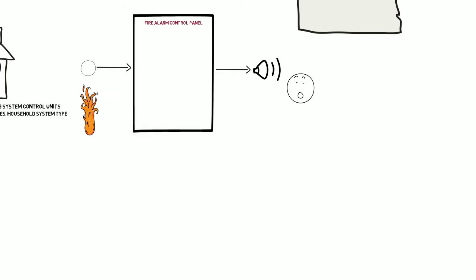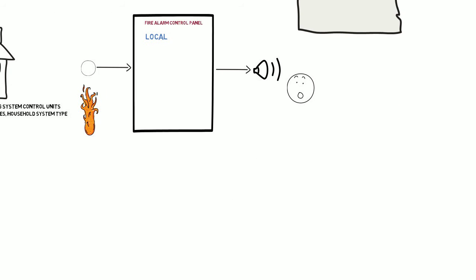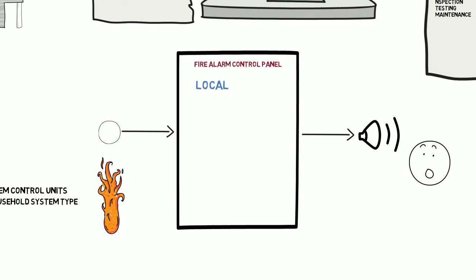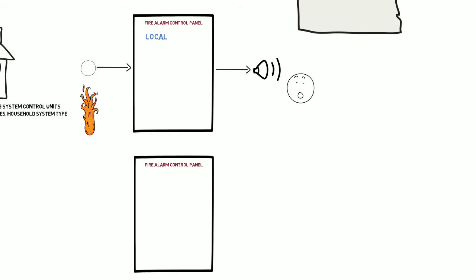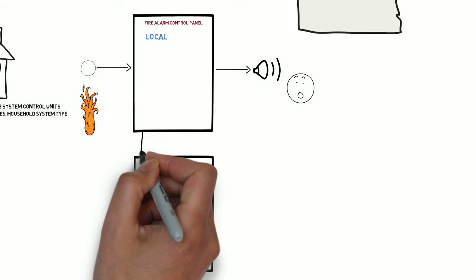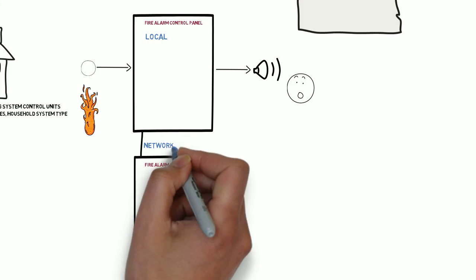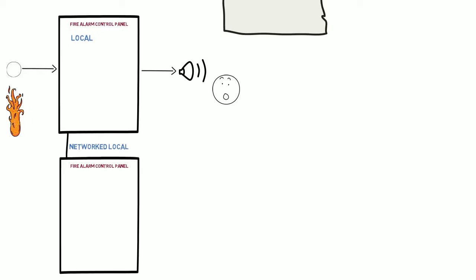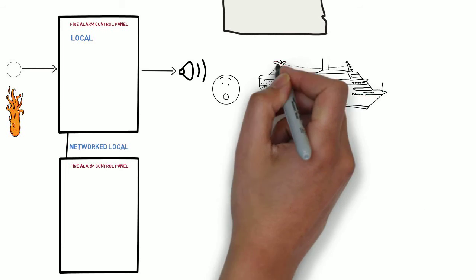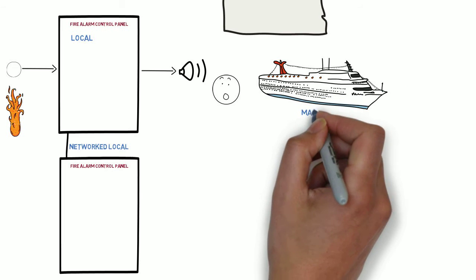Fire alarm control units are categorized by service types. A control unit that detects a fire and notifies people on premises is a local service type. When multiple control units of a local service type can be networked together, they are described as networked local. A local service type control unit that is intended to be installed aboard a commercial vessel is a marine service type.